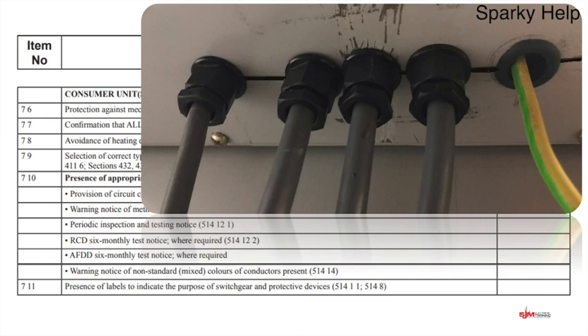If they hadn't put the slot in, and it's recommended about a 3mm slot between the holes, and they're not the straightest in the world, but hey, that's just a job that's been noted, then you'd need to correct it if someone has gone individually. And this goes for single phase or 3-phase or anything, okay?